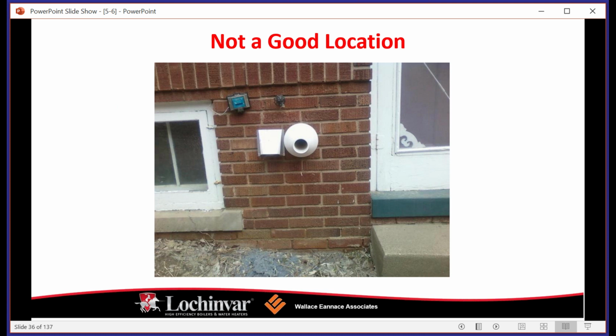We've got a sillcock for water right above it that could potentially just drip water over onto it, and a laundry vent literally right next to it. You can see that there's plenty of laundry lint down on the ground, and I will absolutely guarantee that as this boiler runs, if it's running while the laundry is running, that fresh air intake is pulling laundry lint into our heat exchanger.